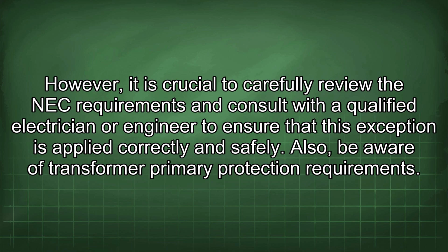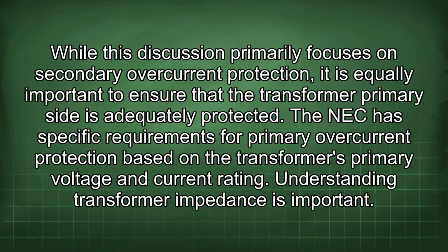Also, be aware of transformer primary protection requirements. While this discussion primarily focuses on secondary overcurrent protection, it is equally important to ensure that the transformer primary side is adequately protected. The NEC has specific requirements for primary overcurrent protection based on the transformer's primary voltage and current rating. Understanding transformer impedance is important.